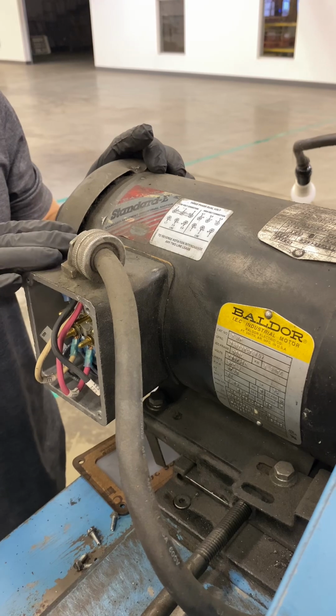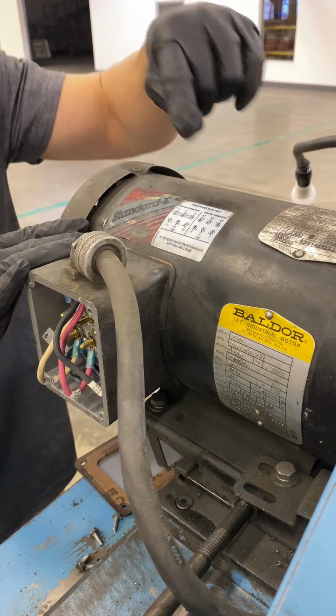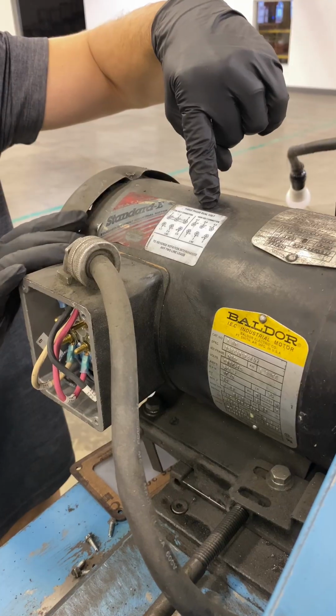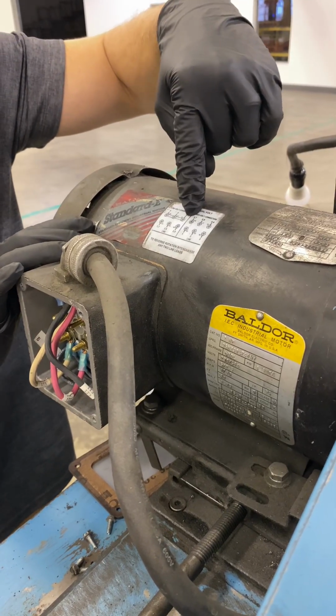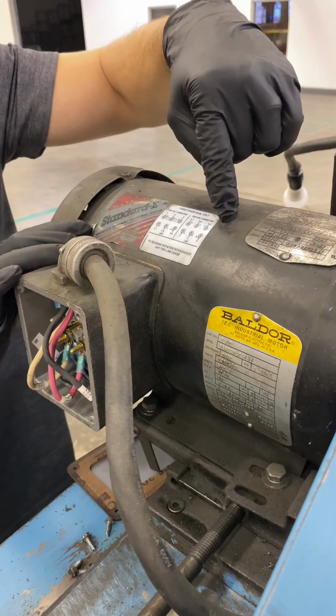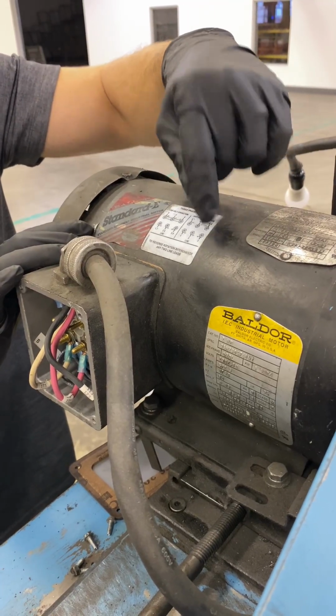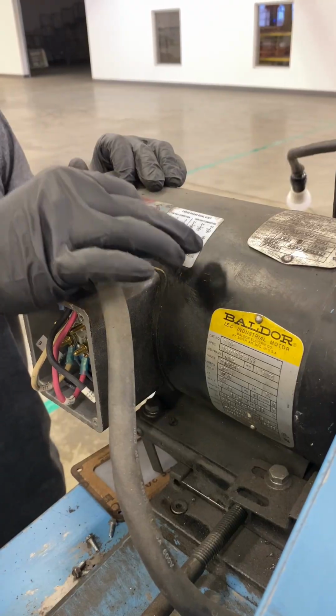How I'm gonna change this to high voltage is just based on this chart that comes on the motor. So I'm gonna be taking 4 to 7, 5 to 8, 6 to 9, and then 1, 2, and 3 are gonna go on to U, V, and W.